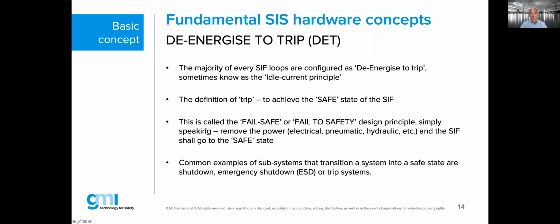So that's also the reason why, when we are talking about de-energize, taking the energy away from your safety function to go to a safe position, we call that a fail-safe principle. In other words, you take away the electricity, or if there is a pneumatic or hydraulic signal, you take away the energy, you remove the power, and your safety function shall go to a safe state. That is one of the fundamental items in the safety industry.